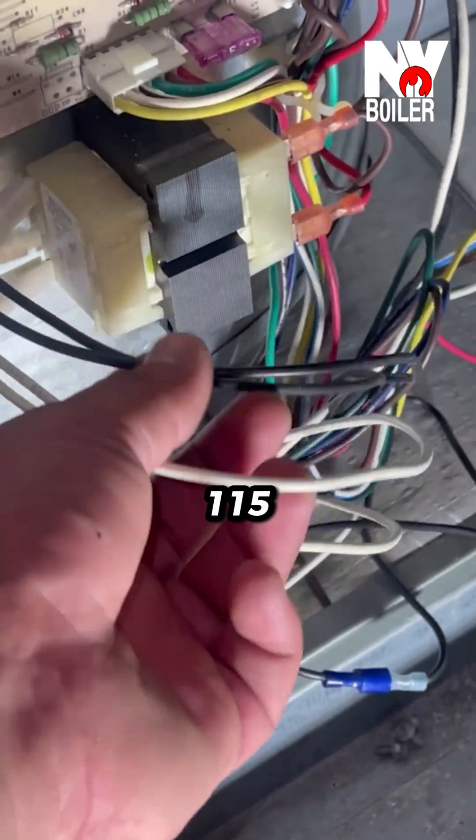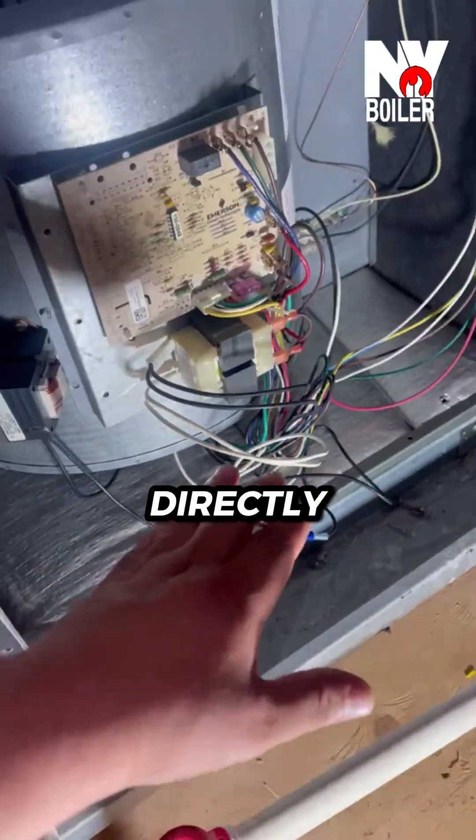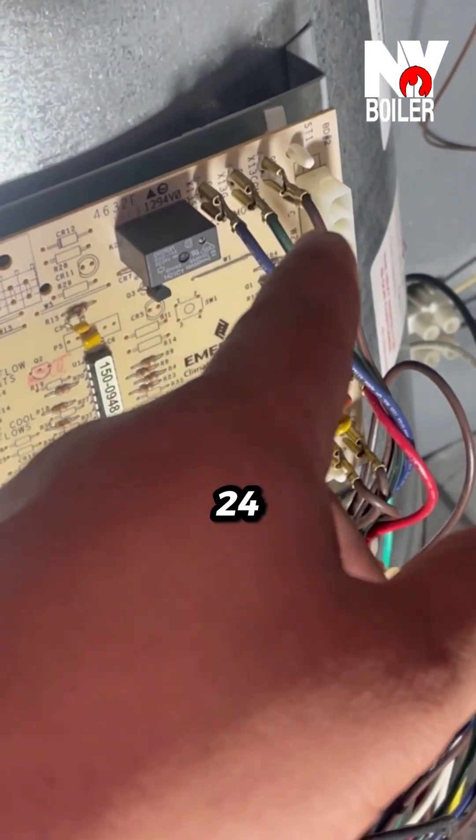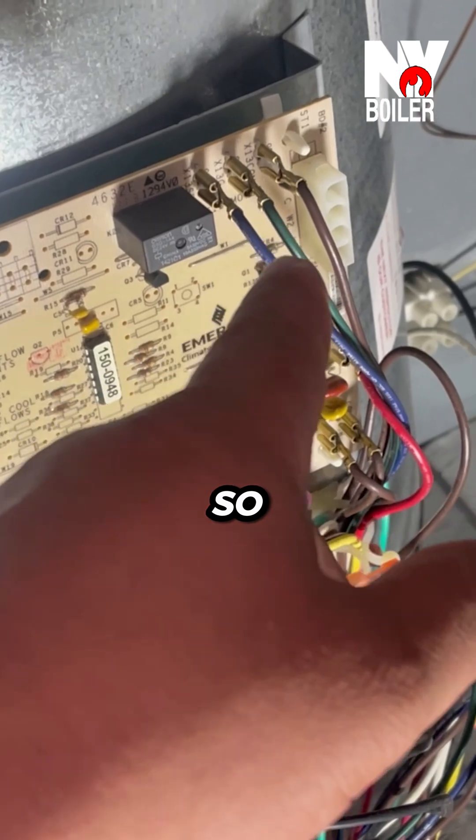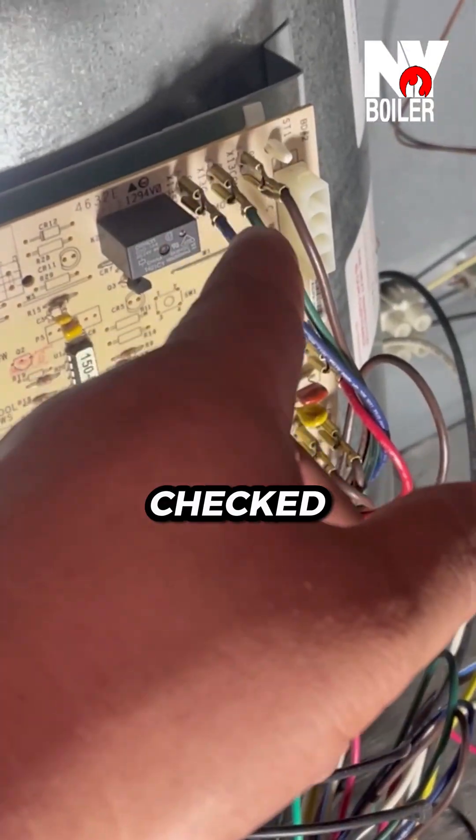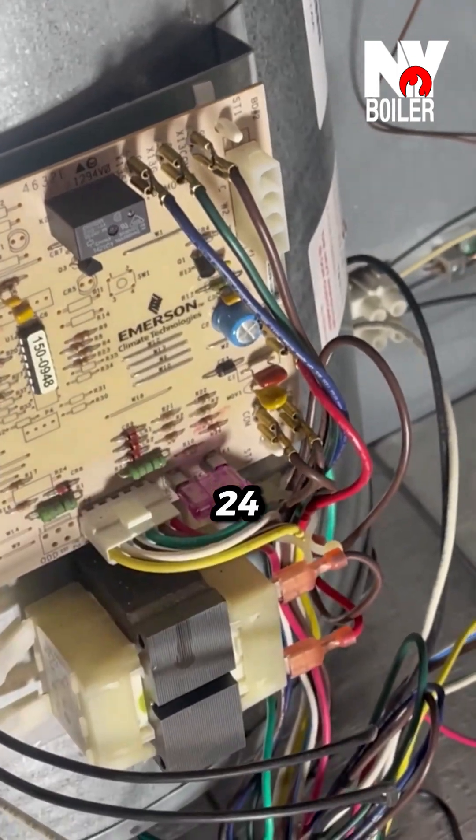So you got 115 volts going directly to the motor, and over here this one gives you 24 volts that powers your motor. So you have a low voltage side and a high voltage side on the motor, and sure enough I checked here that I got 24 volts going directly to the motor.